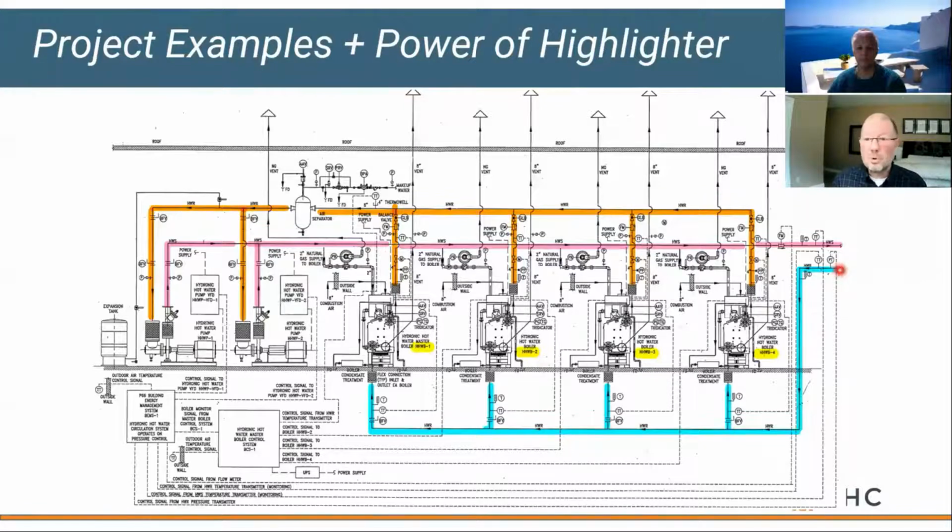So let's just focus on one boiler. We're returning cold. We flow in here through boiler number 4. And as I leave boiler 4, I'm paying close attention. What do we have leaving boiler 4? Well, you'll notice there's a little valve in here, a butterfly valve with an M stamp next to it. Well, M would mean motorized. That's a good thing. Okay, there's my motorized valve.